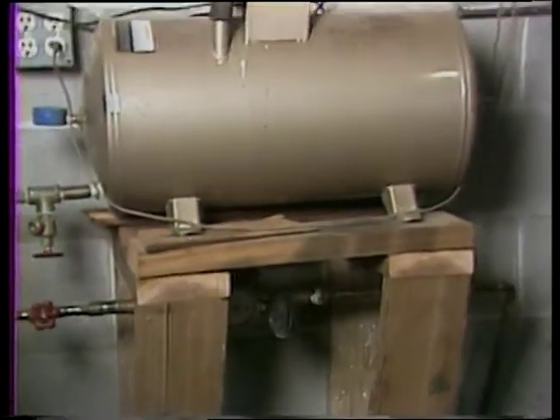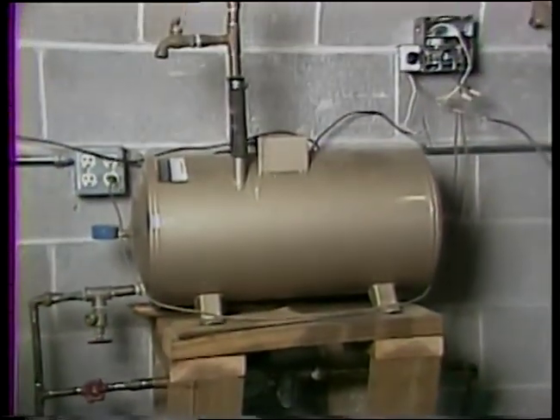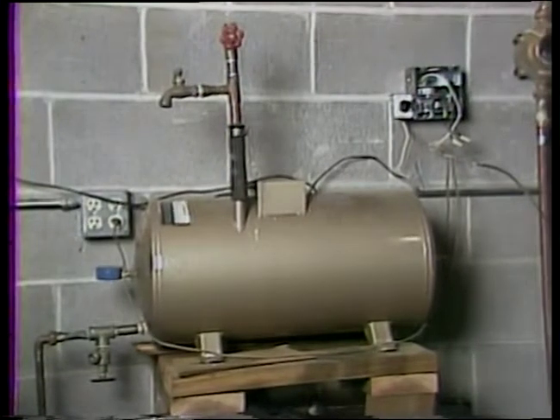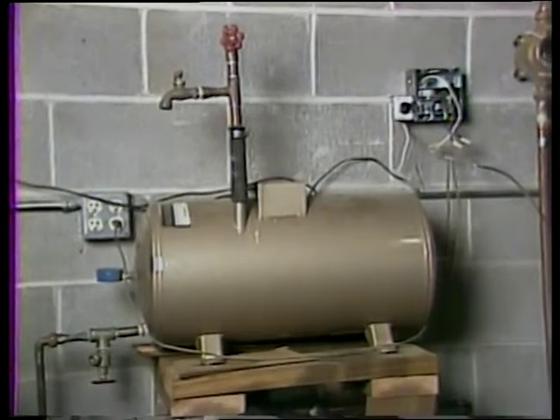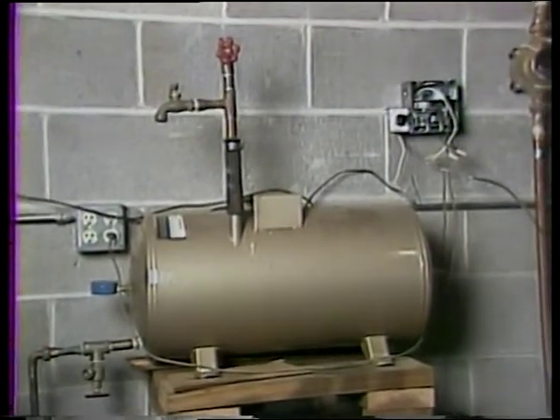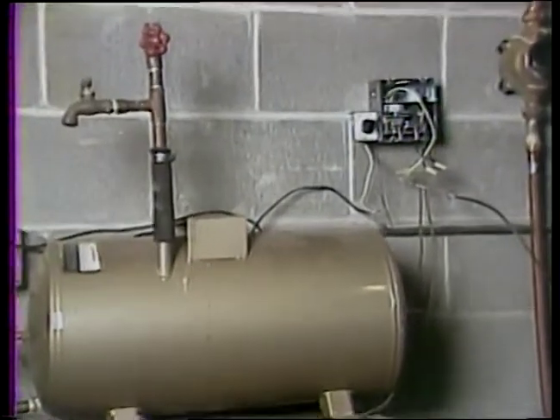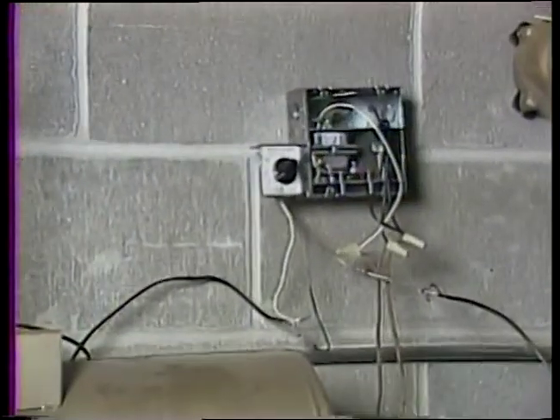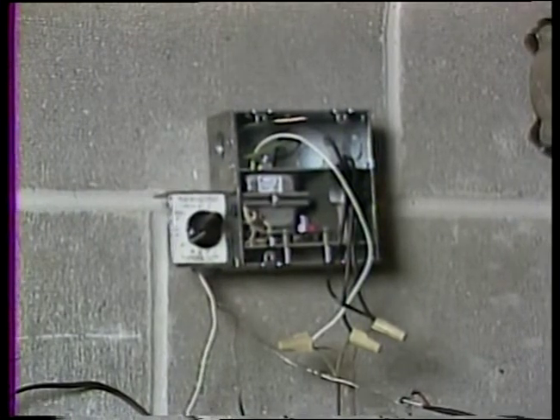Above that solar circulating pump is an expansion tank, which is necessary to allow for the normal expansion and contraction of the water in the closed loop system. And then above that is the differential control unit, which actually measures the temperature at the solar collectors and the temperature in the storage tank. And when the differential is about 20 degrees, the solar circulating pump is turned on.